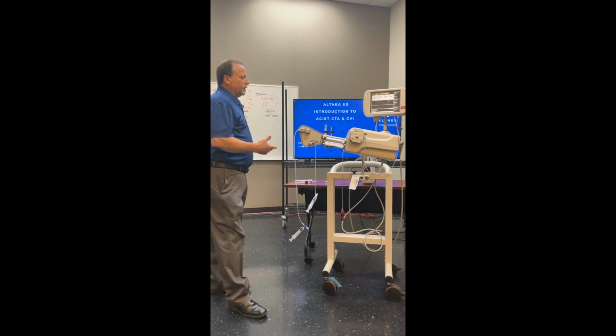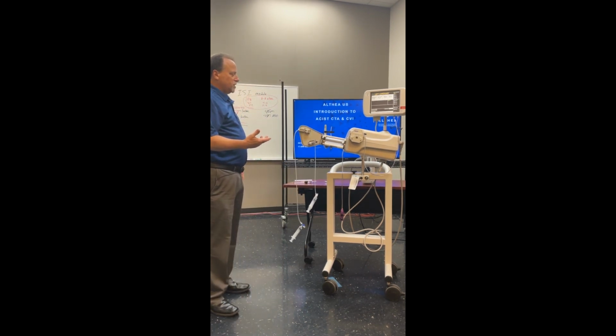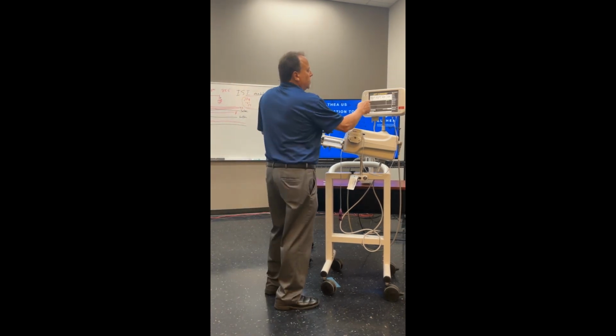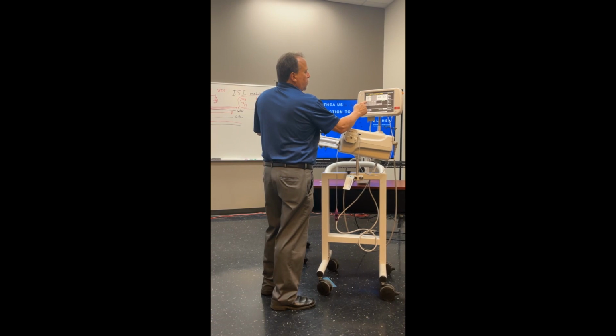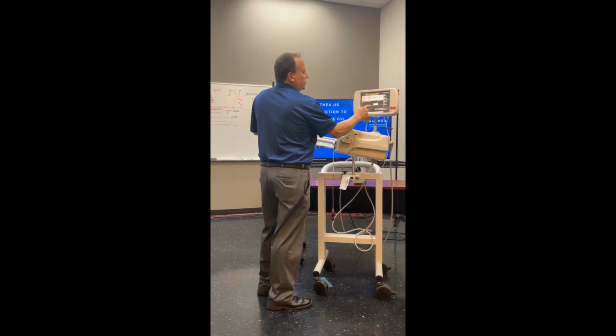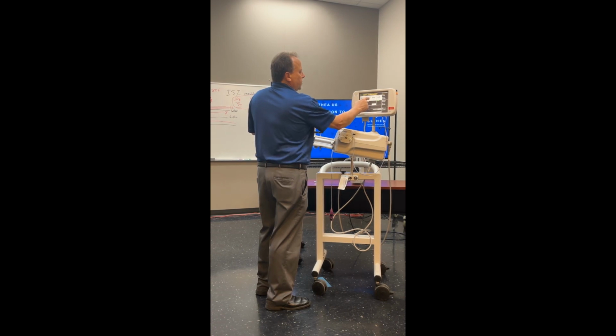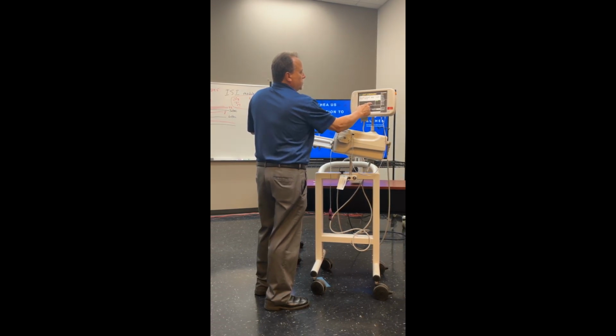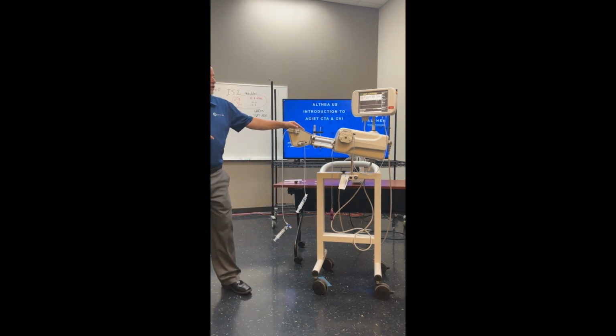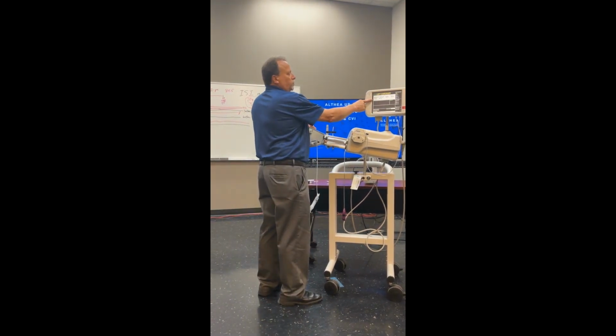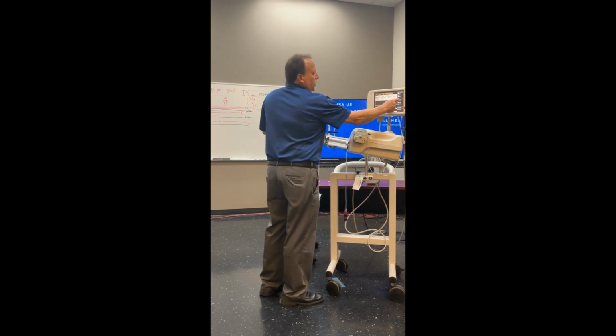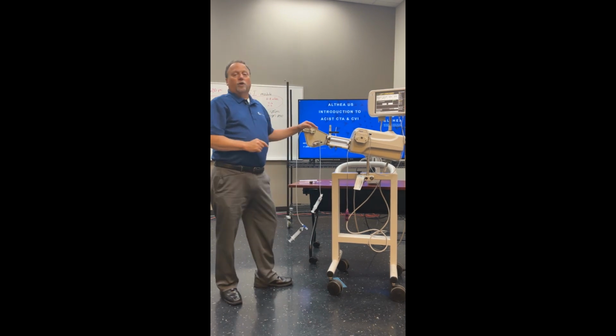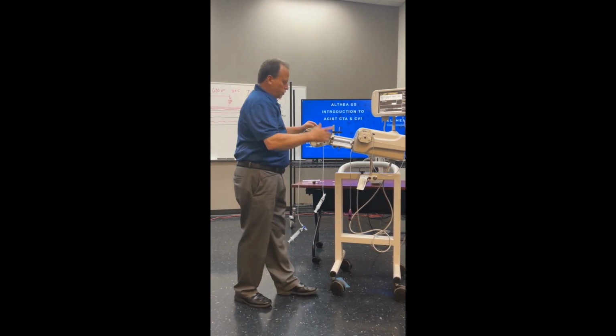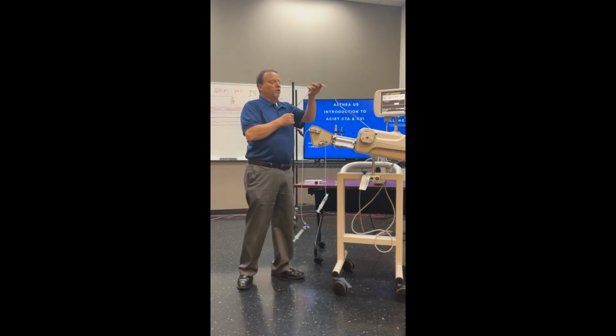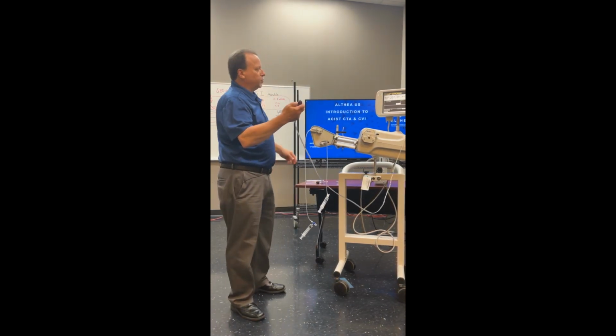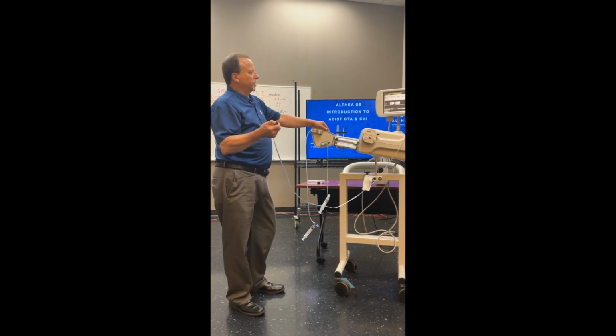So let's go ahead and put in an injection and see how it works with the autofill also. I'm going to do a flow rate of 10, volume of 75, and the PSI, okay, our volume limit is 20, so I'm going to go with 20 then, depending on what we have selected on the procedures. So we're going to do a flow rate of 10, volume of 20. I'm going to hit inject. OK to arm injector. I say OK. It's ready to inject. Now, how do I inject? By pushing the button. I'll push contrast. And it's injecting.